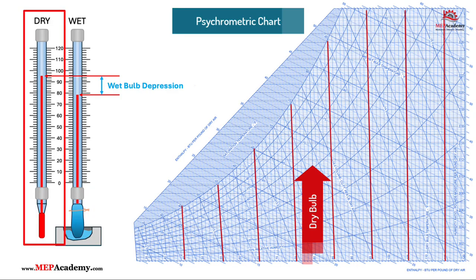Dry bulb temperature is the temperature of the air measured by a regular thermometer without considering moisture. It's measured using a standard thermometer exposed to the air but shielded from direct solar radiation. Dry bulb temperature is what people commonly refer to as air temperature, and it indicates the heat level of the air, making it crucial for thermal comfort and HVAC system design.